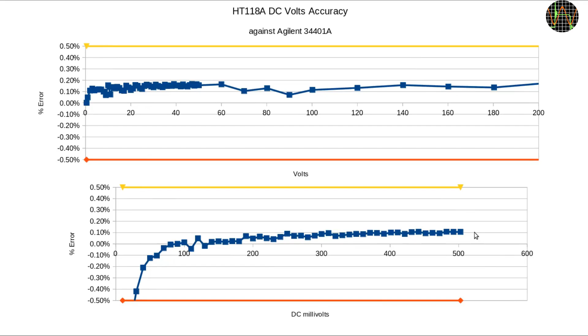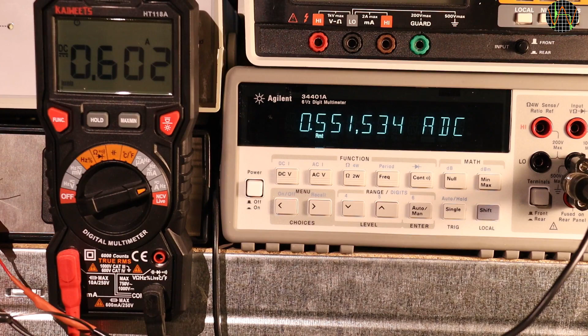While I can only test to 200 volts, I believe that covers most of the cases where the HT118A will be used. Within that range, the HT118A is a lot more accurate than its 0.5% DC volts, and its millivolt range is even better. Across the whole range, the HT118 is basically within just 0.15% of the Agilent, a very good result. I use the same method for DC currents by programming the power supply to work in constant current mode and using the current in series through both the HT118 and the Agilent meter. But because there are 3 ranges, I need to do this for amps, milliamps and microamps.